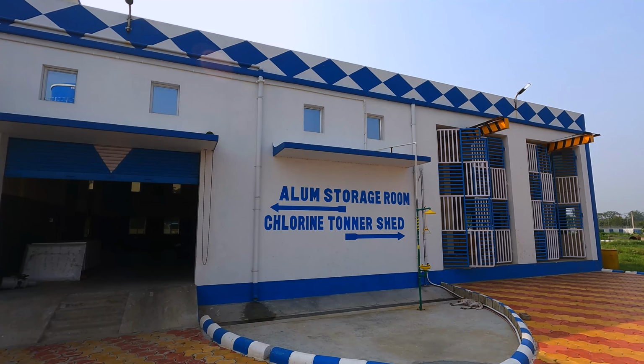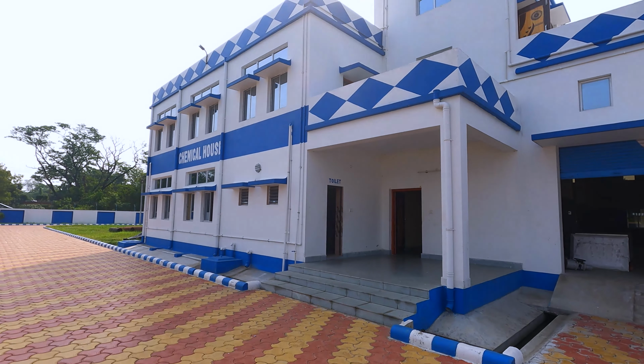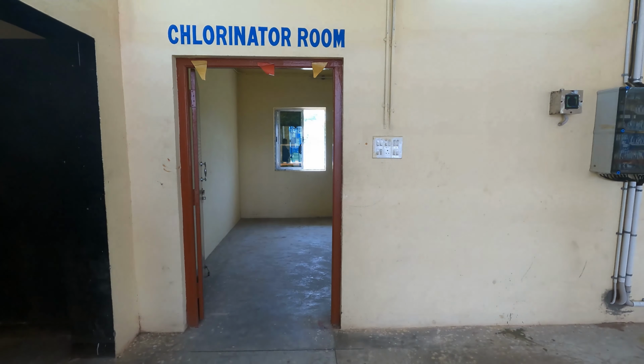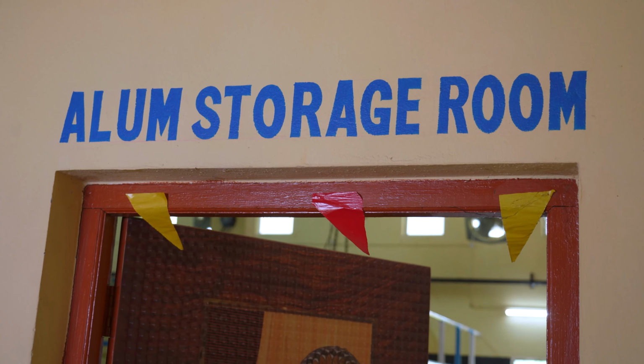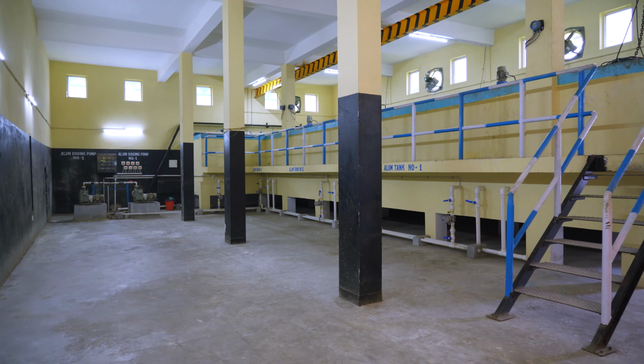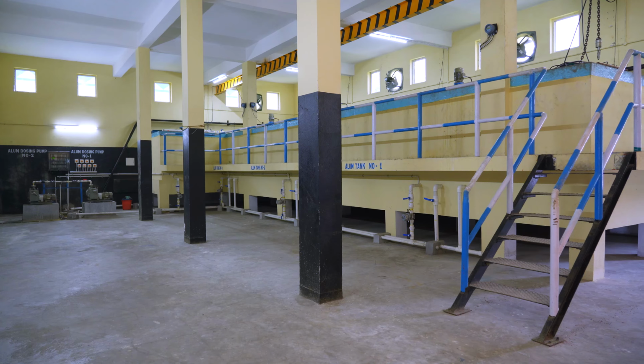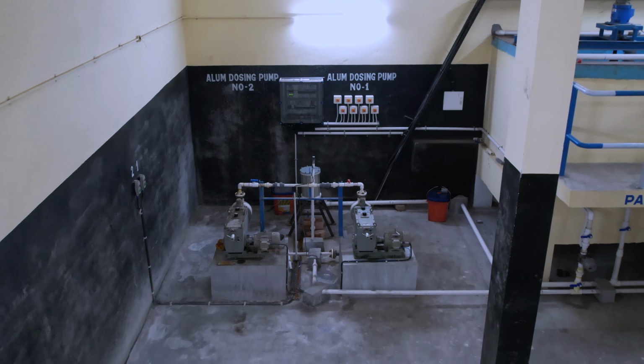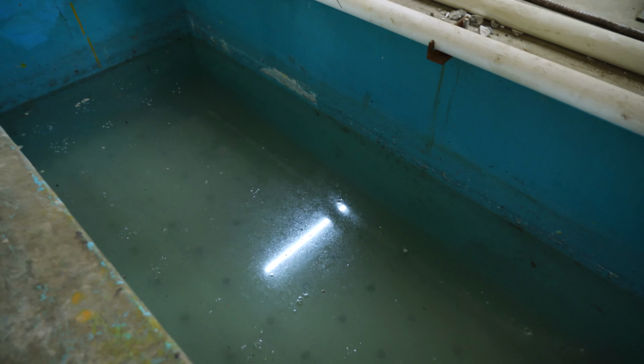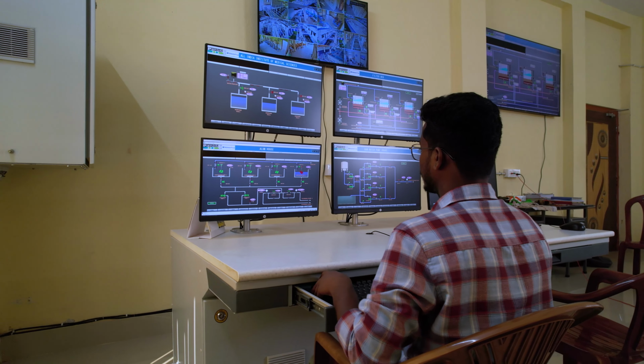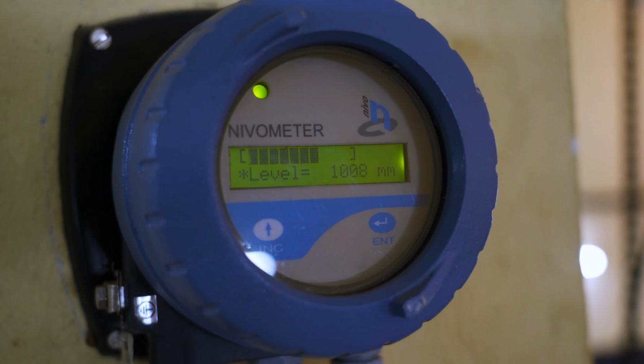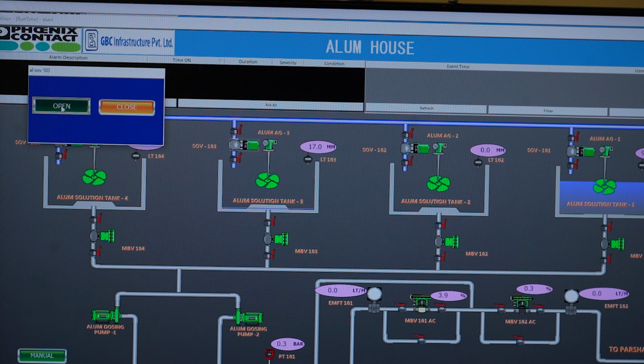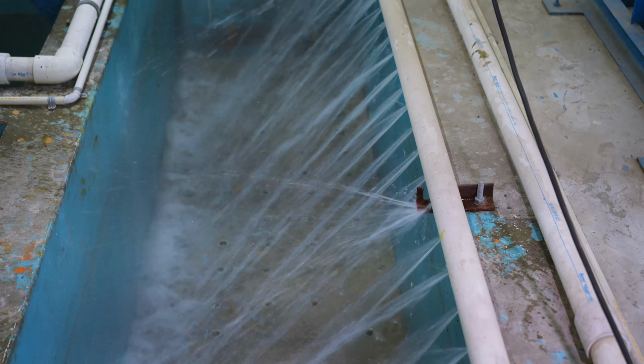The alum mixture preparation and chlorine gas mixing with water are being executed at chemical house. The quality of raw water changes with season. Accordingly, the alum solution is made in different strength in different alum tanks. The level of water in the tanks are being monitored by level transmitters and subsequent refilling of tanks is being executed by the SCADA system.